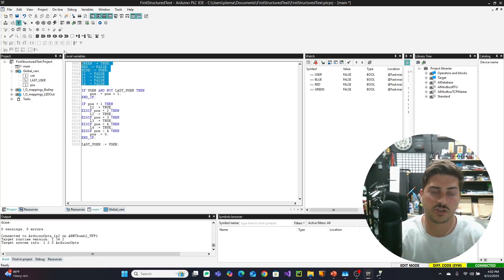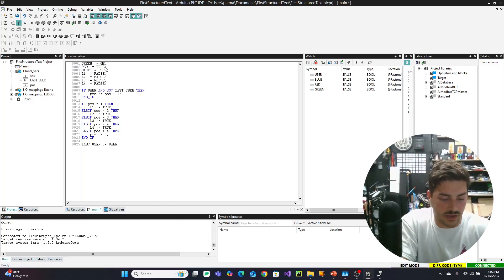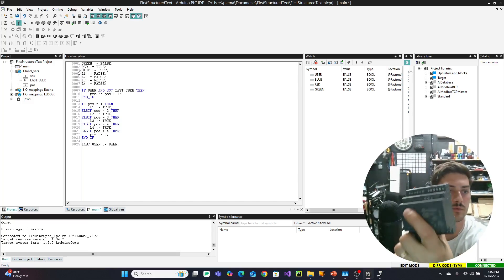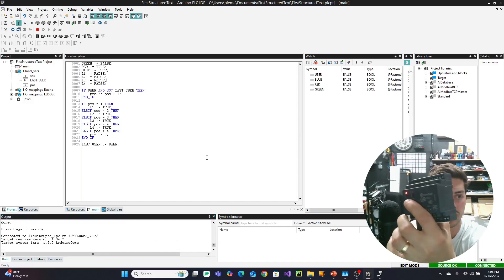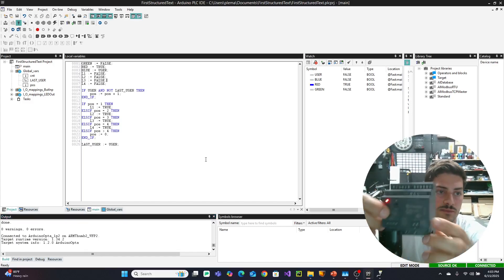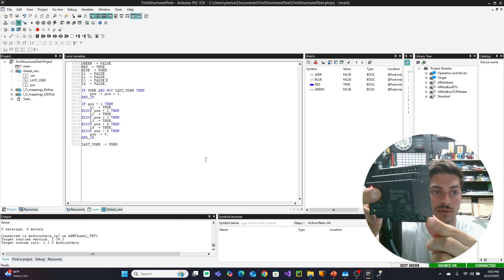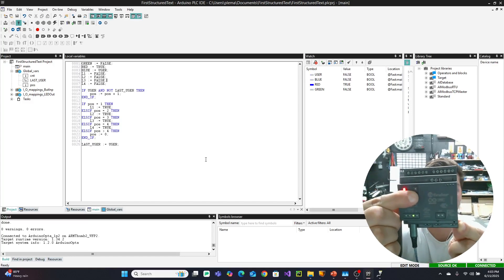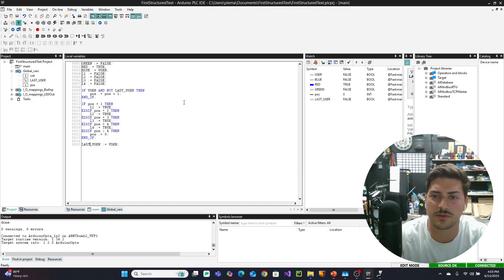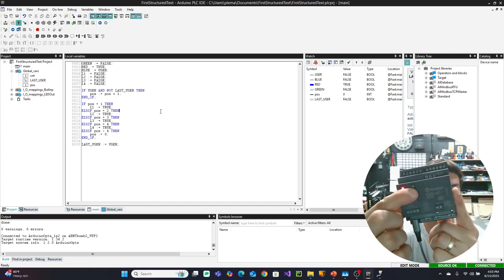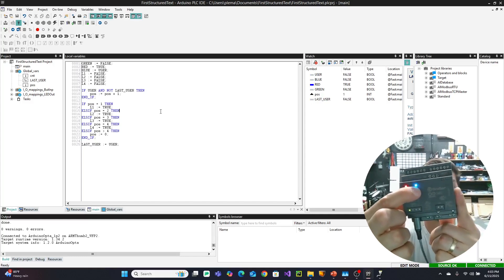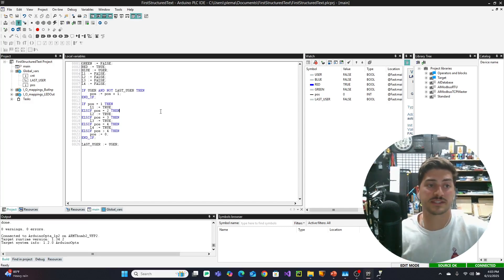Let's see if we made any errors. Looks good, because I'm a professional. And the red lights on, nothing else is on, which makes sense based on the code that we wrote. And let me try to get this framed properly. I'm going to push the button, and the blue light turns on and position one turns on. Push it again, position two turns on. One, three, four, zero, one, two, three, four, zero. And you can add position to your watch window, add to watch, as well as last user if you really want to, as well as L1 through L4. And now as you're cycling through pressing the button, you can see the value of position change every time you push the button, and blue user and last user all change almost exactly together. But so that's really fun. That's basic sequencing. A very common way to write controls sequencing is in step one, do a series of things, and then once you've checked some condition like pressure, flow, temperature, move to step two and then do a series of things in step two. So this sort of sequential move through a position value is actually a really great introduction to PLC programming.